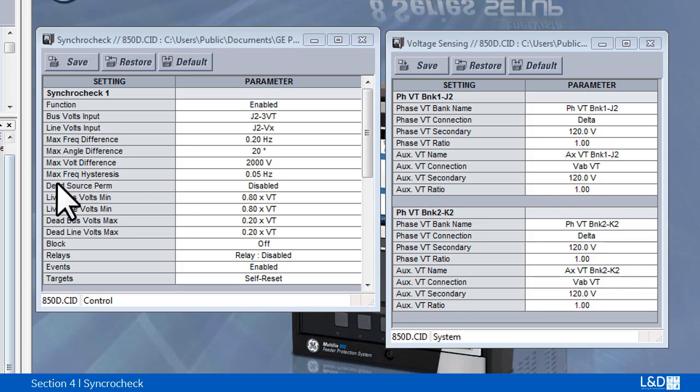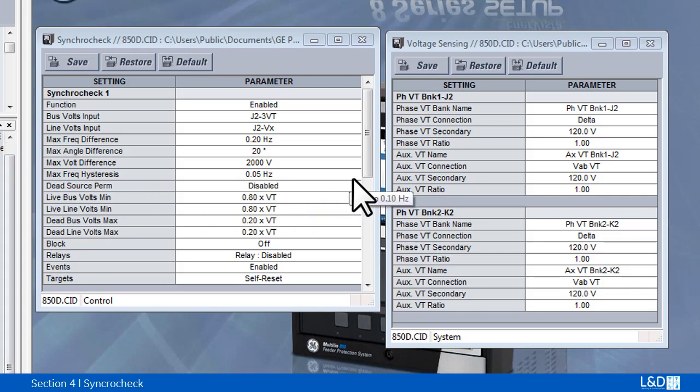For the hysteresis setting, once the synchro check element has operated, the frequency difference must increase above the synch max frequency difference plus the synch max frequency hysteresis sum in order to drop out the relay.